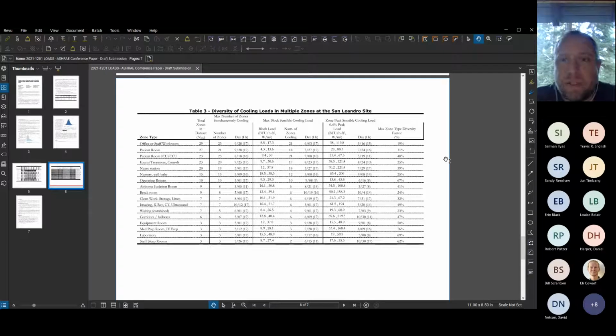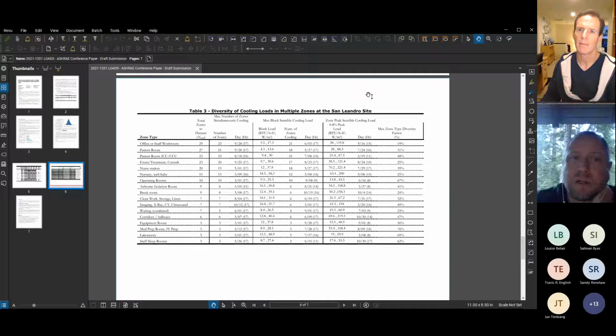But in the case of the calculation, essentially what we did is we actually, through the data set, looked at all the peak loads that ever occurred for that space type and took a 0.4% peak load out of that data set. And so that was what we used for the denominator for this sampling. But we also have the ability, at least in San Leandro, to see the actual design load from the design documents, so we can compare it against that as well for the individual zones. In terms of delta T, we use the same for this 0.4% peak load, using that as the denominator. We use the same calculation method as for the actual loads that we're experiencing. So it's the supply air temperature coming off of the box relative to the room temperature.